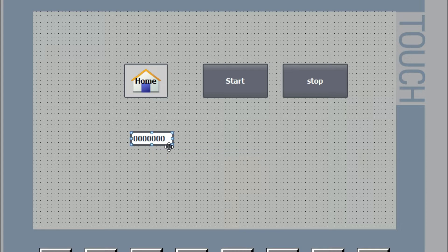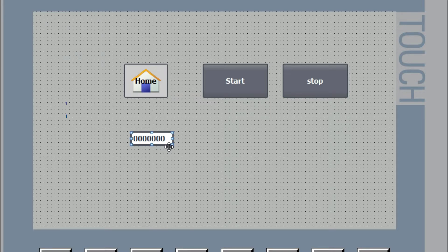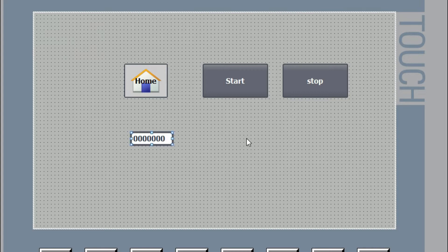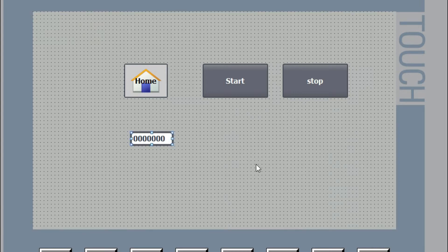To give a setpoint to the PLC we always need two types of tags. We can use a data block tag — that means a local variable tag — or we can use PLC memory. We cannot use analog input. We will use the data block address tag. We will take two IO fields: one as an input field to send a setpoint to the PLC, and one to read a value from the PLC to the HMI.